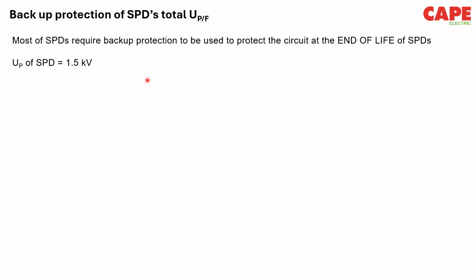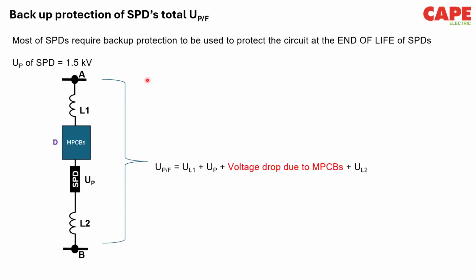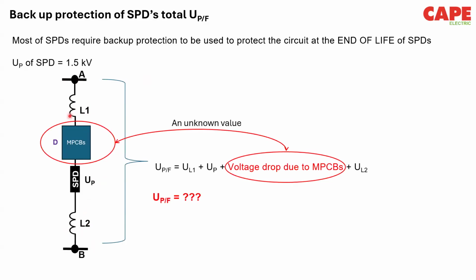But the problem happens when some people or some manufacturers say that you can use an MPCB to give this backup protection. What happens is, I know the voltage drop at level 1, length L1, and I know the voltage drop at L2, and I know the voltage protection level of the SPD. But what I don't know is the voltage drop at the MPCB or any other circuit breaker. It is an unknown value. So generally when you provide an MPCB or some other circuit breaker, I cannot guarantee that an SPD will work because the voltage drop here is unknown.